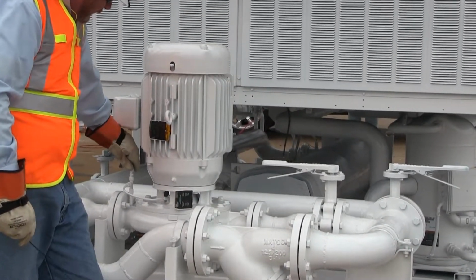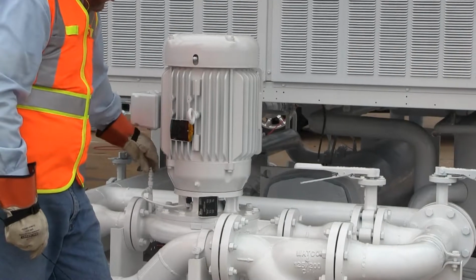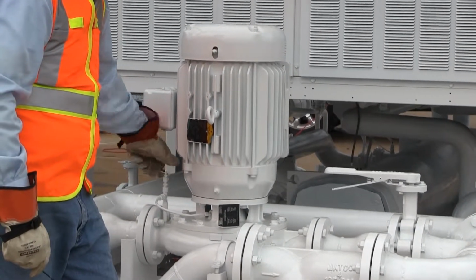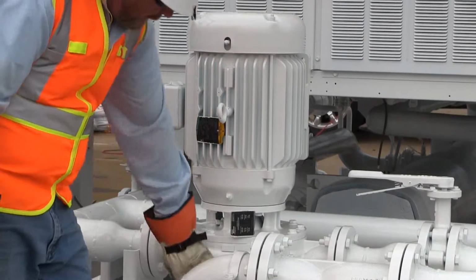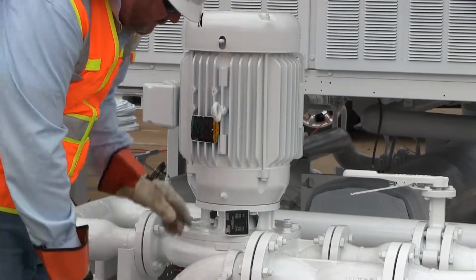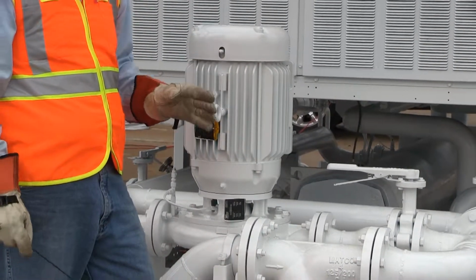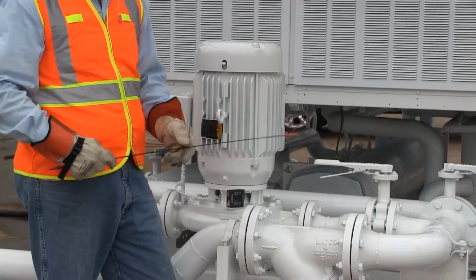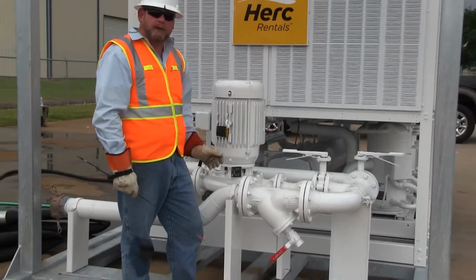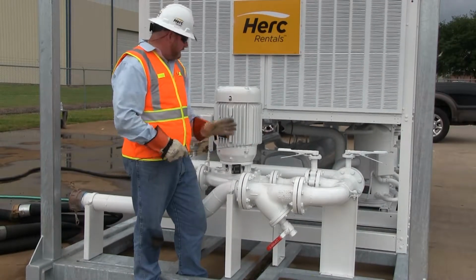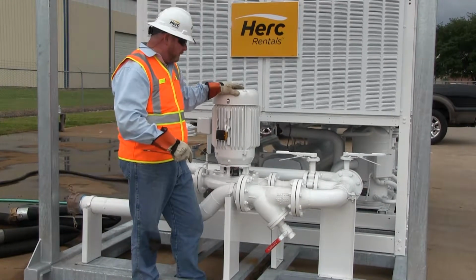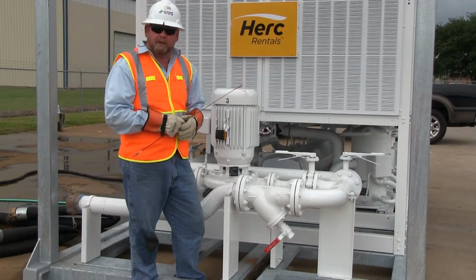Please note that your air bleed for your pump volute is right here at the top. When we fill the system up, we'll be bleeding air off of that. Then on the bottom of the volute here, up underneath this brace, is the drain valve for the pump volute for winterization. That's where you're actually going to drain the water out of there. So this completes our circulation of our loop. So now we're going to go ahead and get the plumbing finished and start filling the system with water.